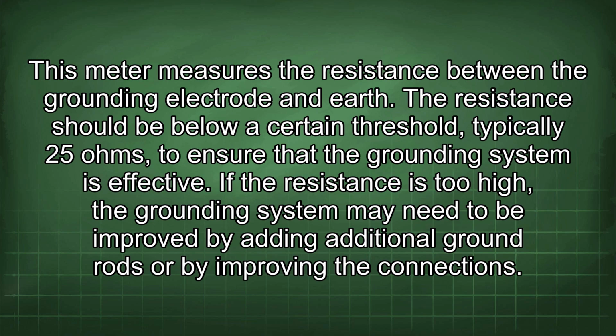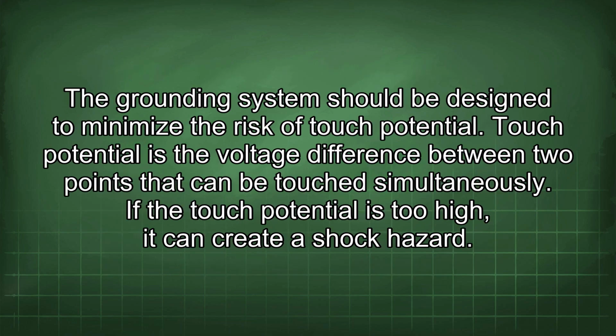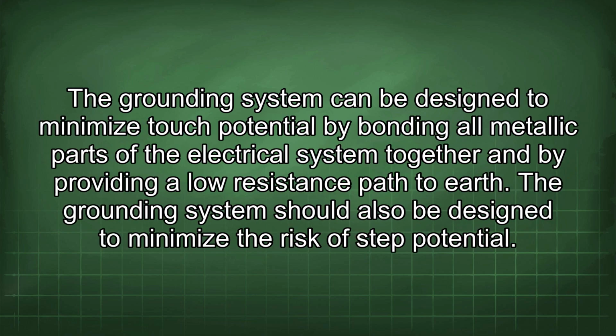The grounding system should be designed to minimize the risk of touch potential. Touch potential is the voltage difference between 2 points that can be touched simultaneously. If the touch potential is too high, it can create a shock hazard. The grounding system can be designed to minimize touch potential by bonding all metallic parts of the electrical system together and by providing a low resistance path to earth.